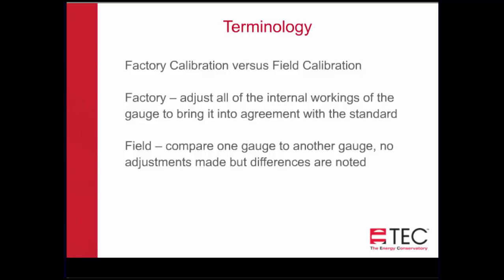So factory calibration versus field calibration. Factory is that we adjust all of the internal workings of the gauge to bring it into agreement with the standard. And we'll show you what that means. Now, the field calibration check is when you're comparing one gauge to another, but no adjustments are actually made. So the ability to bring a gauge that's out of calibration can only be done here at the factory, because that's all done with a computer calibration algorithm.